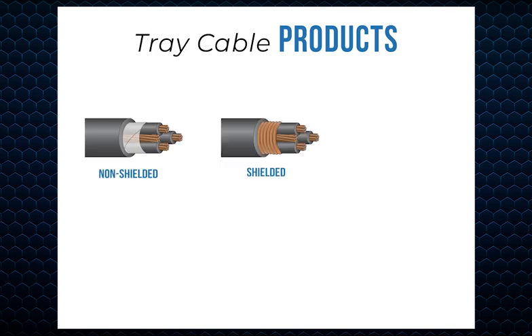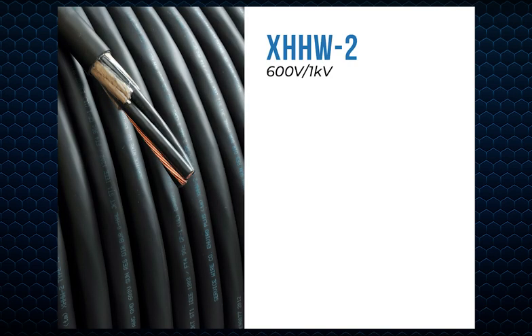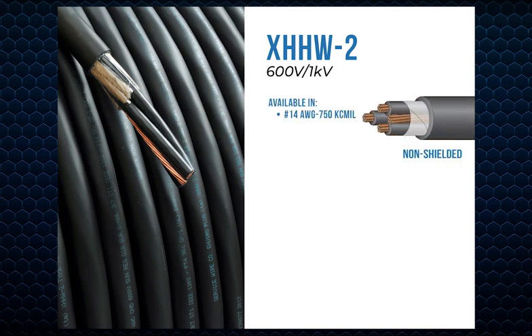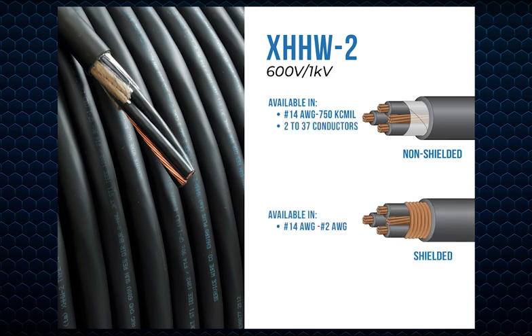Service Wire manufactures 3 different types of tray cable: non-shielded control tray and power cable, shielded control tray and power cable, and variable frequency drive cable. Service Wire offers XHHW 600V/1 kV tray and power cable with PVC, Service CPE, or EnviroPlus low smoke zero halogen jacket. Non-shielded cable is available in 14 gauge through 750 kcmil, 2 to 37 conductors, while shielded cable is available in 14 gauge through 2 gauge, 2 to 19 conductors.